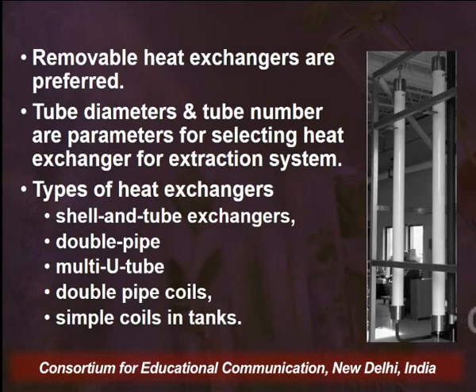Now, whatever tubings are involved in manufacturing the heat exchanger, the number of the tubings and the diameter of the tubings involved in setting up a heat exchanger are very critical. And these are the important parameters for selecting the heat exchanging unit for an extraction system. Because if we are using tubes of less diameter, then obviously to attain the full efficiency of the exchanger, we have to increase the number of the tubes. And once we increase the number of the tubes, the cost factor increases. Second, as soon as we increase the number of the tubes, we have to employ more joints and more couplings in the system, which again are a major source of malfunctioning of the unit.